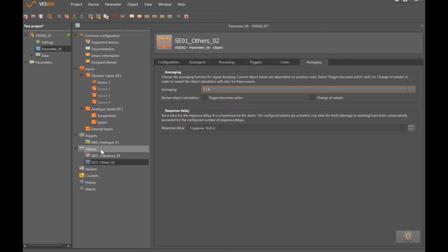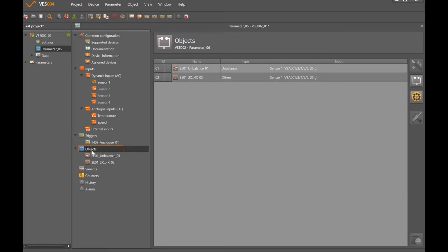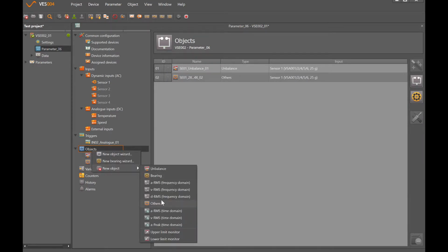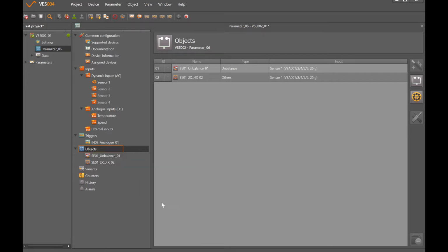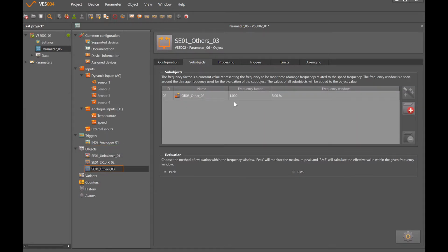Okay, I'm just going to right click there and rename that so it means something. I could have done that in the window to the right here, but I'm going to change that from 2x to 4x. Okay. So the next one, we're going to set up to look for looseness, rotational looseness on the machine. So this time we want to set up sub-objects between 2 and 10 times the speed.